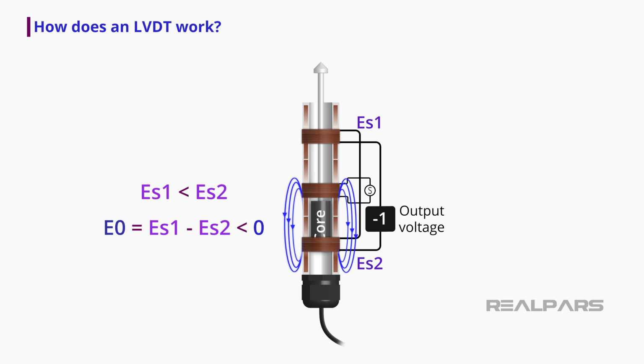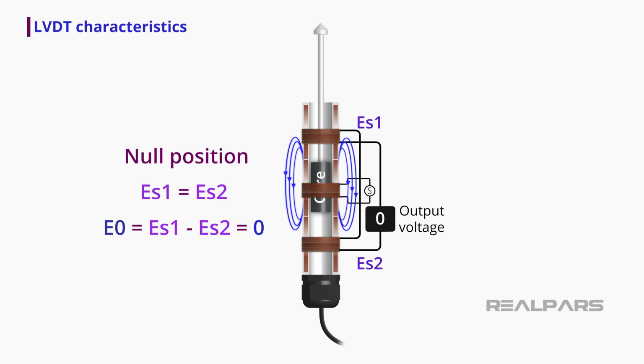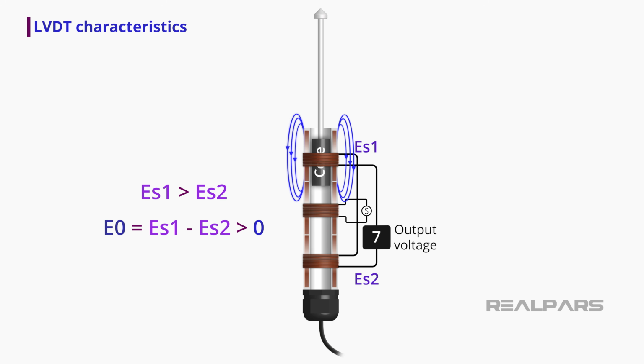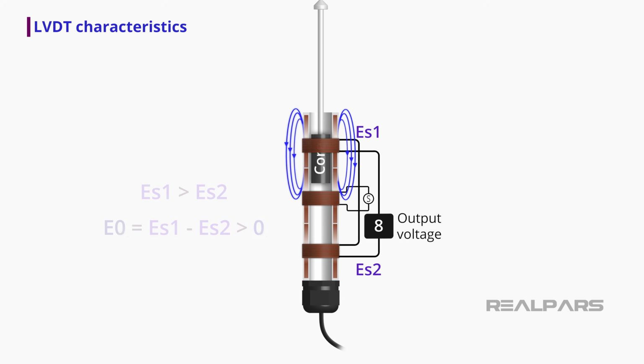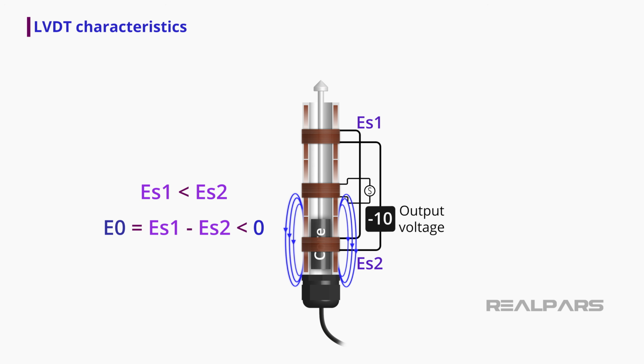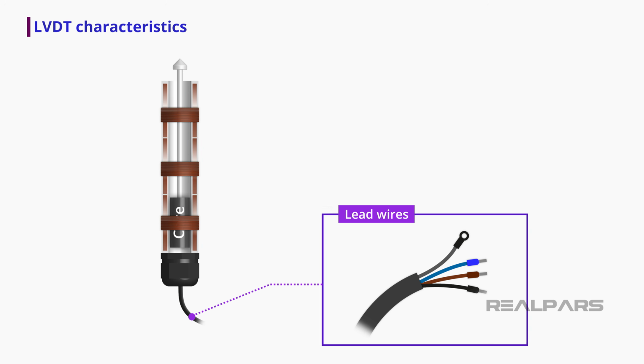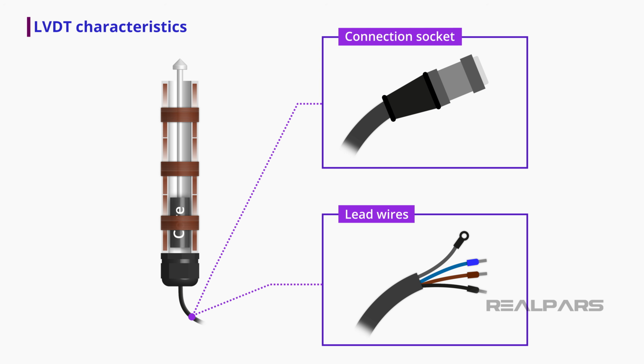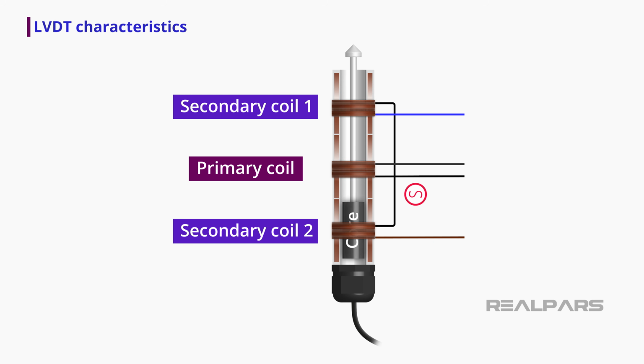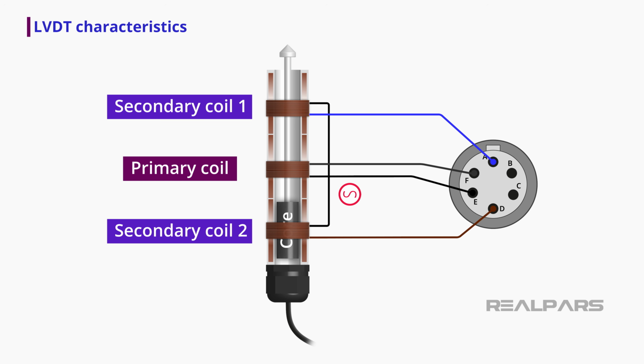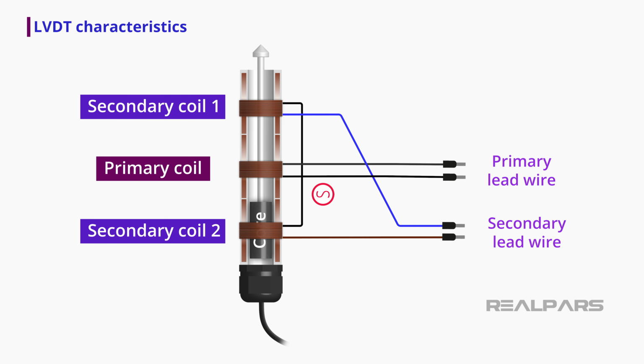When it moves downwards, the induced magnetic flux on the upper secondary winding is less than the induced magnetic flux on the lower secondary winding. This results in a negative output voltage. Due to those characteristics, the direction in which the body is moving and the distance can be determined by observing the voltage output increasing or decreasing, and its negative or positive value. LVDTs can have lead wires or be provided with connection sockets. As both secondary coils are typically wired in series, the sensor has 4 wires or 4 connections in its connection socket. However, some LVDTs will provide the secondary coil lead pairs separately.